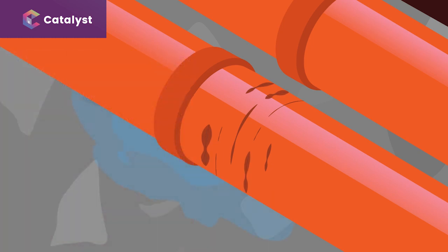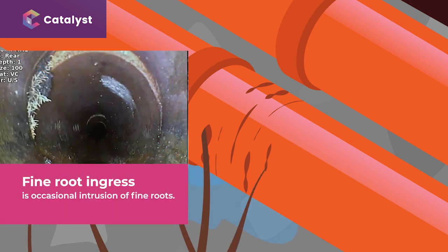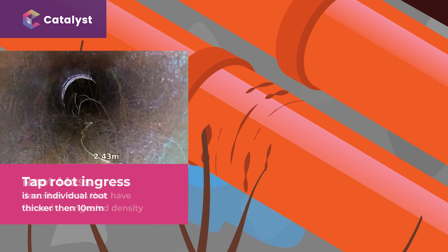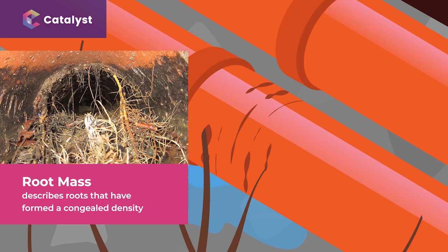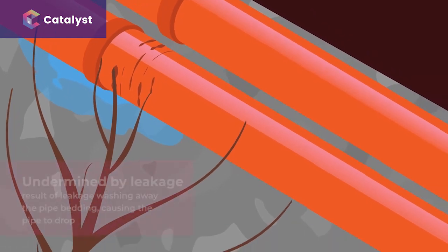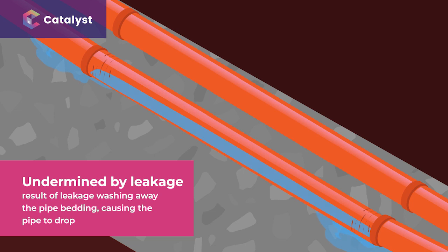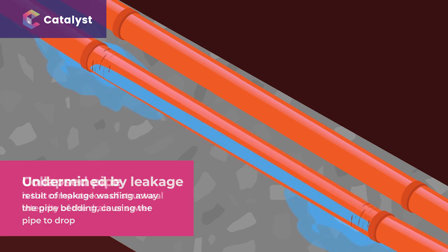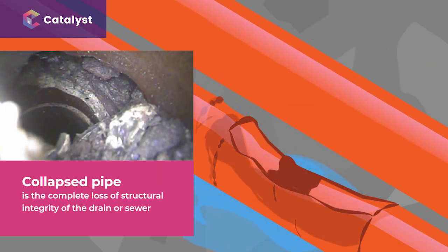Root ingress is coded in three main ways. Fine root ingress is occasional intrusion of fine roots. Tap root ingress is an individual root thicker than 10 millimetres. Root mass describes roots that have formed a congealed density. Undermined by leakage is where a drain or sewer is leaking and the escaping water washes away the bed of the drain or sewer causing it to drop. Collapsed pipe is a complete loss of structural integrity of the drain or sewer.